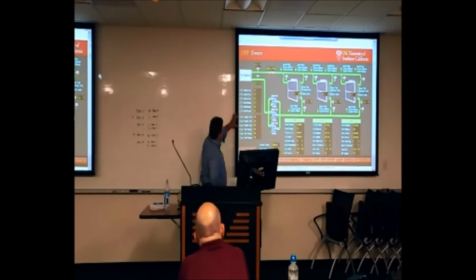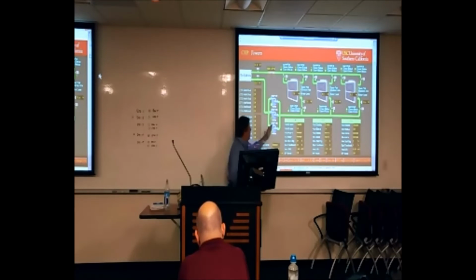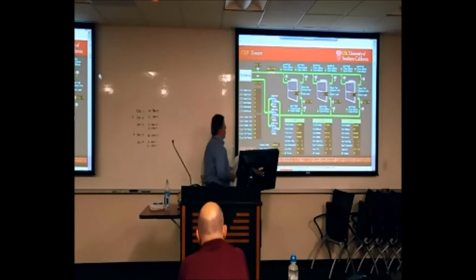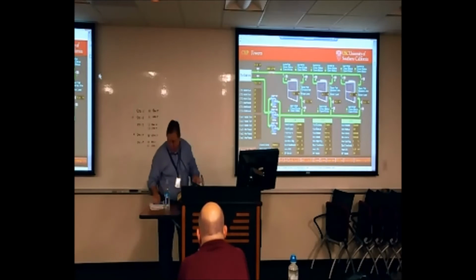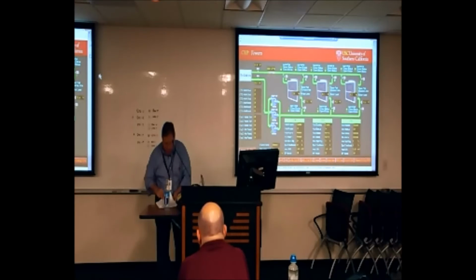Also built into the pump logic is a condenser water pump maintenance switch. So if one of the pumps were down for maintenance, that pump could be put into maintenance, and it'll flash an alarm that it is in maintenance. The pump is down, and it'll also just run through the existing 2 pumps that are left in. It'll secure it the same way the alarm point is going to secure that pump. So by putting it in maintenance, it just secures it and won't be called for until you hit the maintenance switch off, and then it comes back into service. Now the cooling towers have a little more sophistication to the alarms.